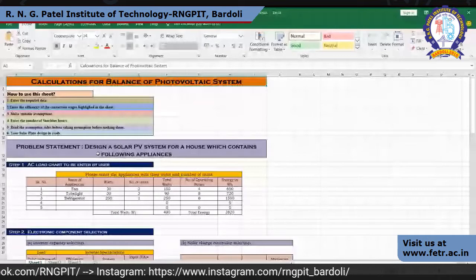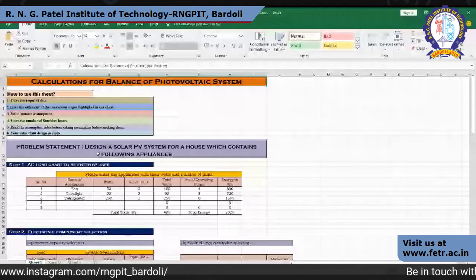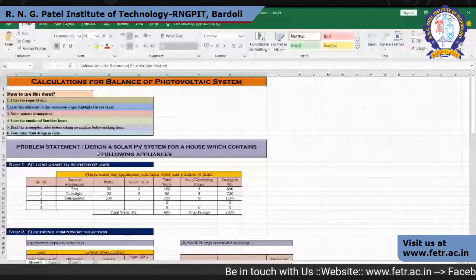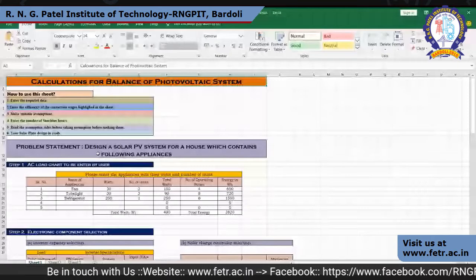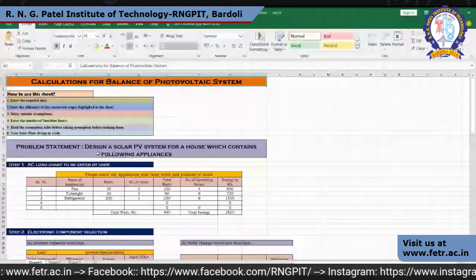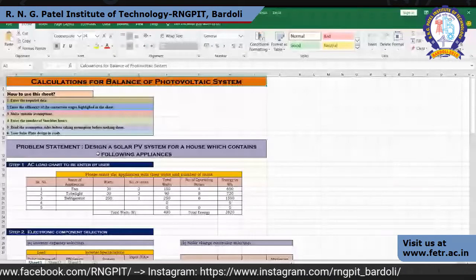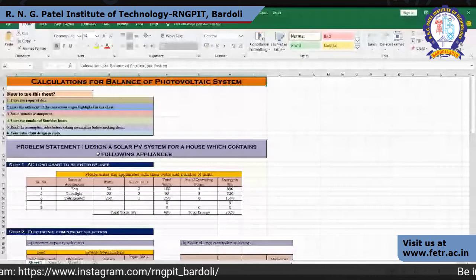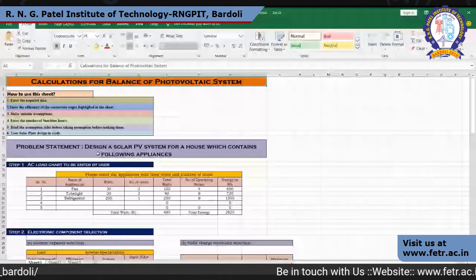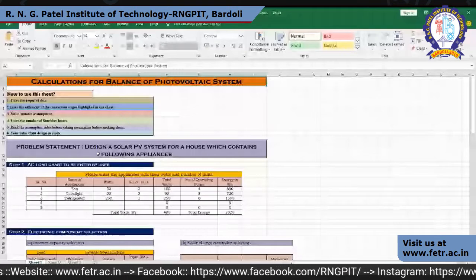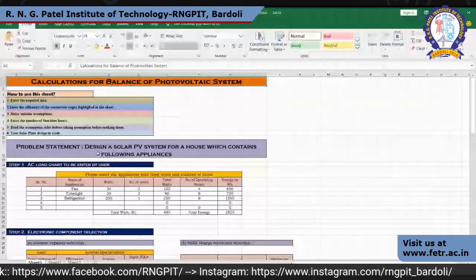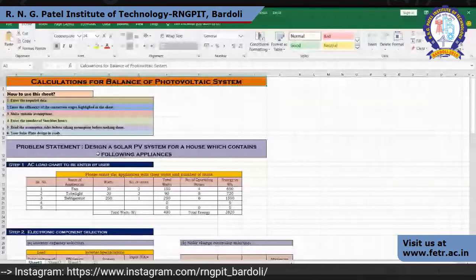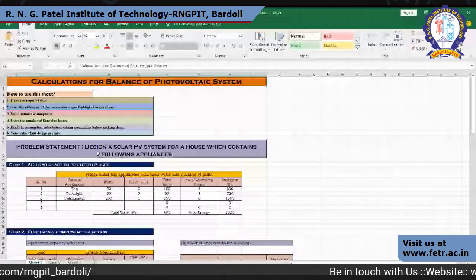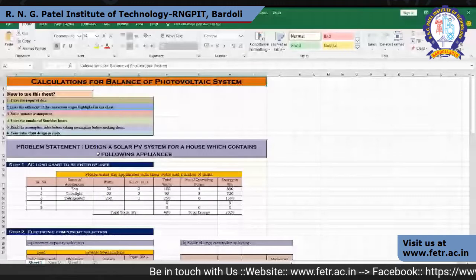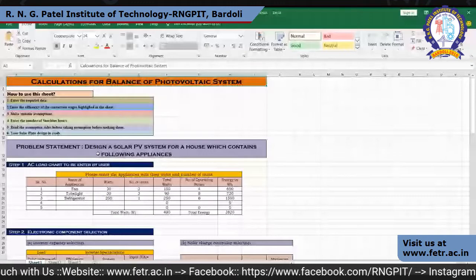According to that, you will set the wiring depending on wattage and voltage. So your current rating and voltage rating, this is a DC current rating. Depending on current, you select the gauge of wire, that is SWG, standard wire gauge sheet available. We have already calculated the alternating current voltage capacity; obviously it's a single phase system at home. The current would be computed from power upon voltage, so 990 by 230 is 4.30, approximately 4.3, and similarly you will get the current and power both.